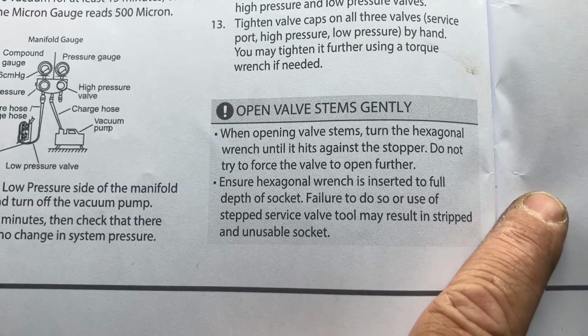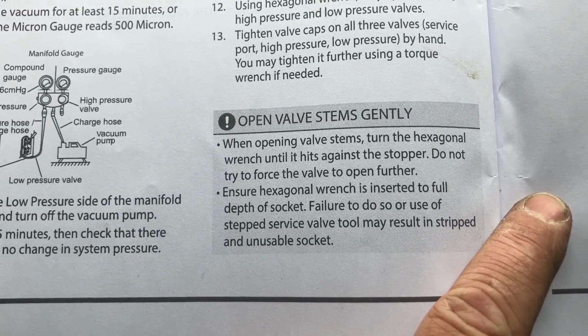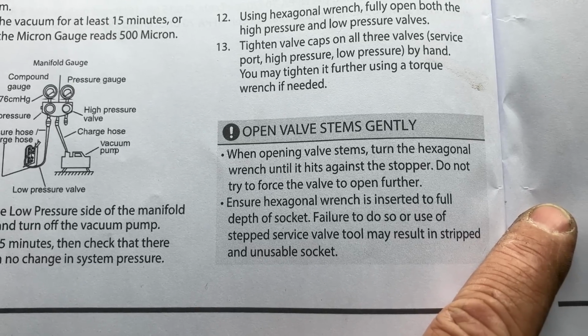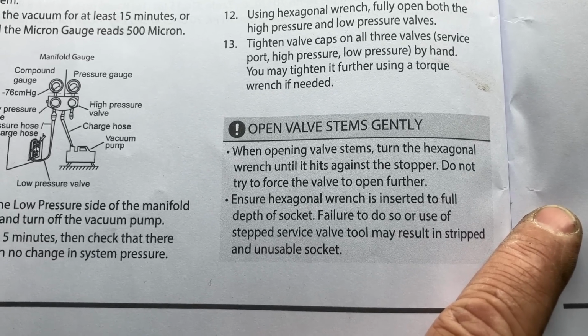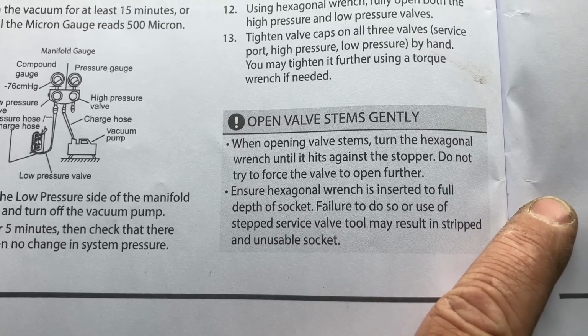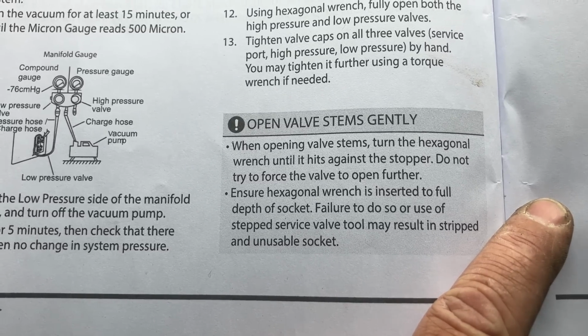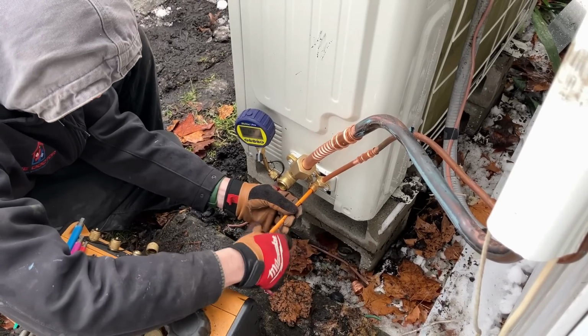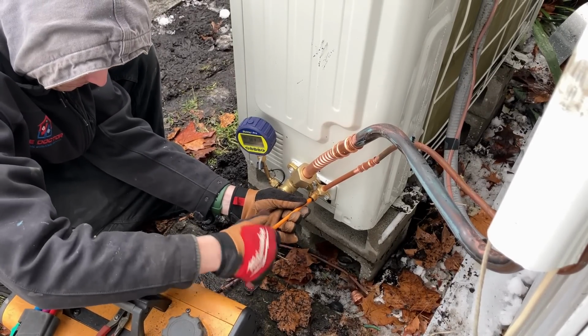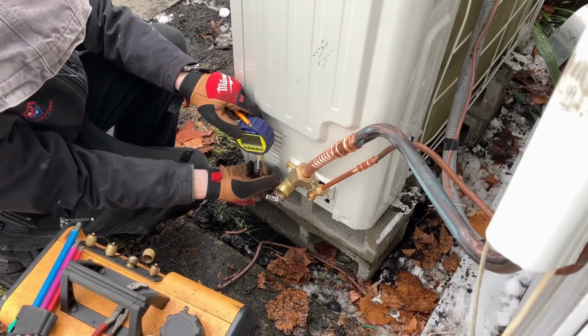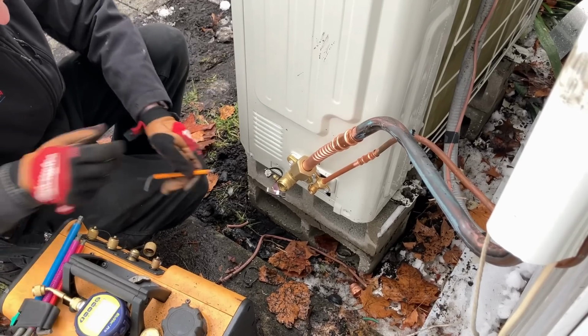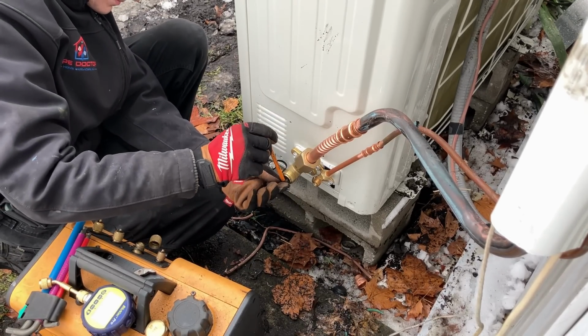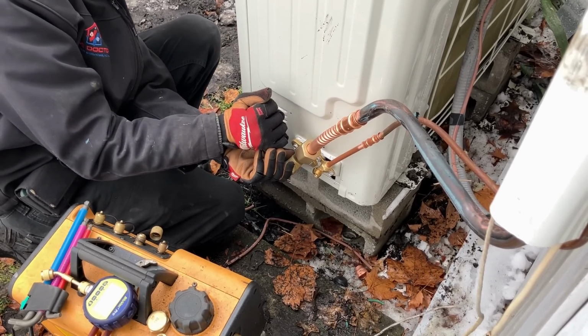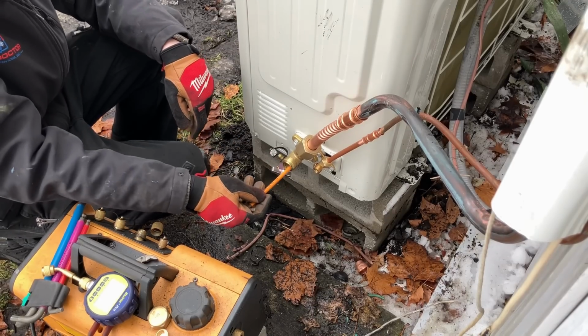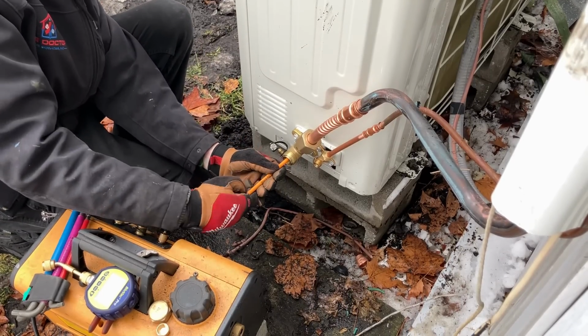Okay. Page 24. Open valve stems gently. When opening valve stems, turn the hexagonal wrench until it is against the stopper. Do not try to force the valve to open further. Ensure the hexagonal wrench is inserted to full depth of socket. Failure to do so, or use the stepped service valve tool, may result in a stripped and unusable socket. Removing the micron gauge so we don't get high pressure hitting it. Now Daniel's going to open up the 7/8 service valve, gently opening it, and now fully opening or back seating the valve.